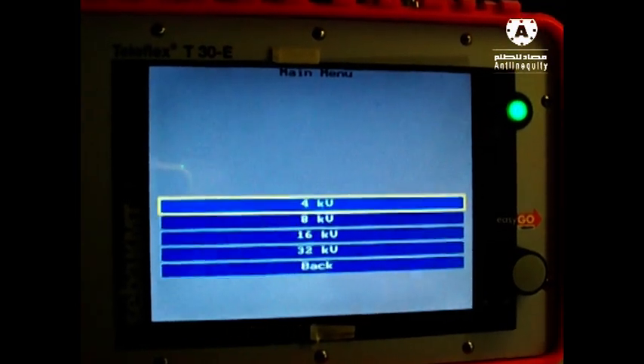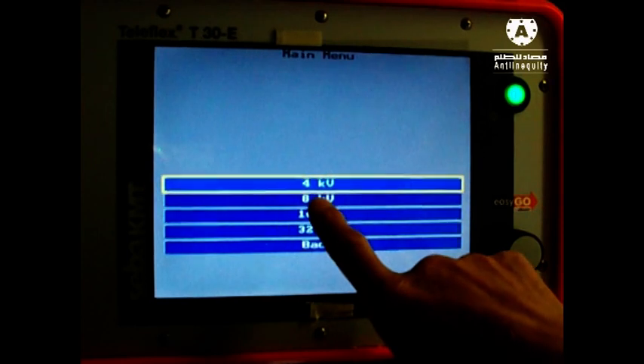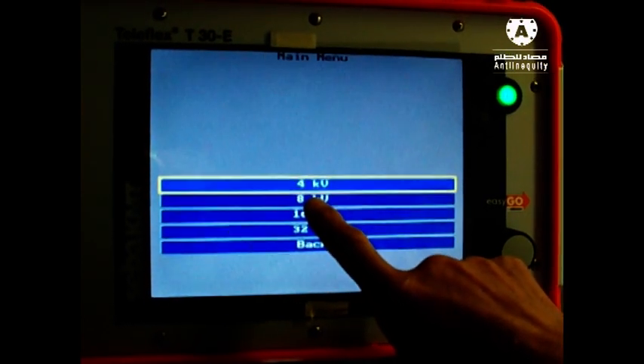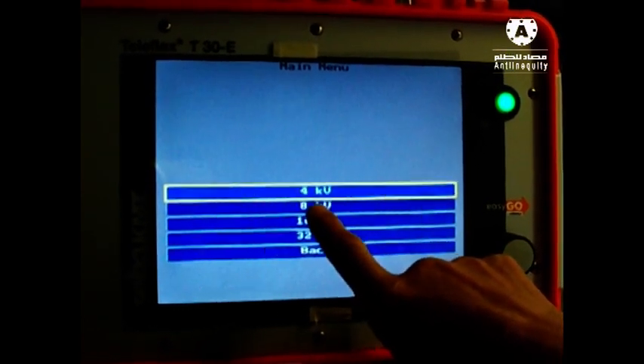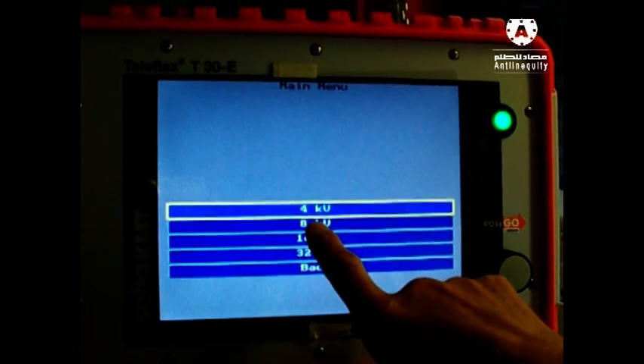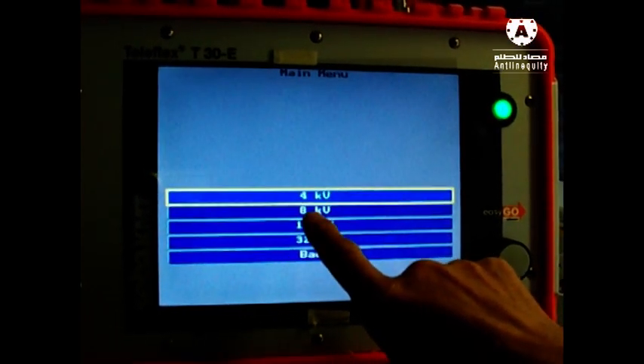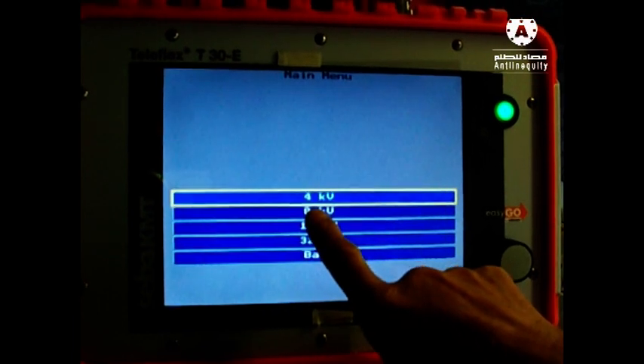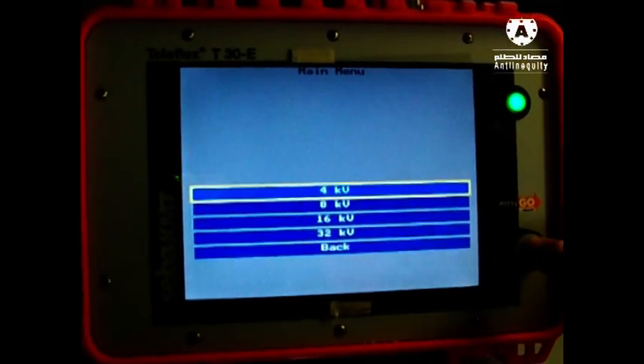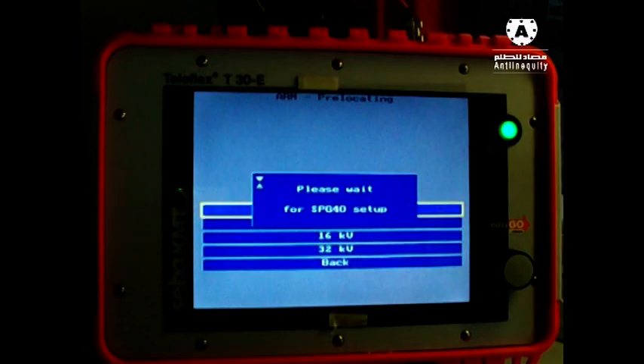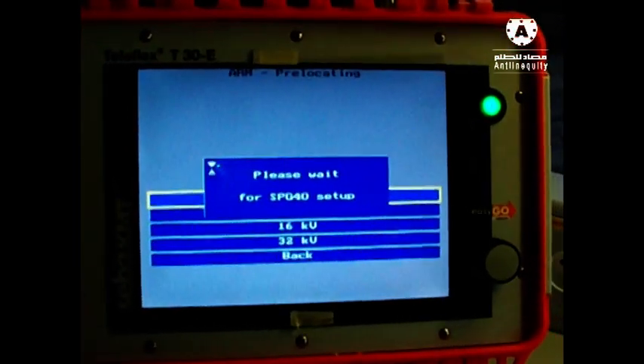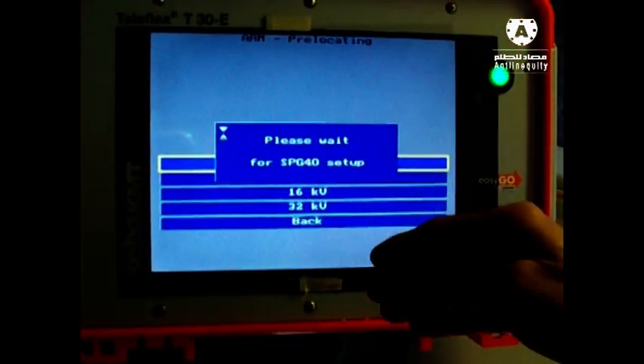Adjust the output voltage. We must remember, by insulation test we get the information our output voltage or breakdown voltage was less than 2 kV. So in this case, it is a short kind of cable, we can adjust 4 kV. If it is a long distance cable and the breakdown voltage is much higher, you can also adjust 16 or 32.